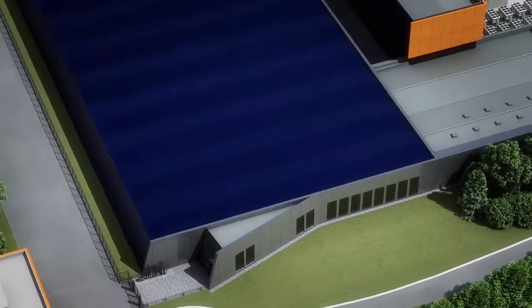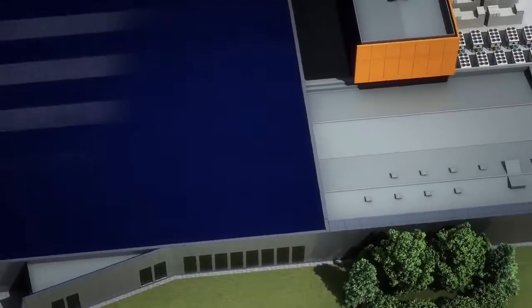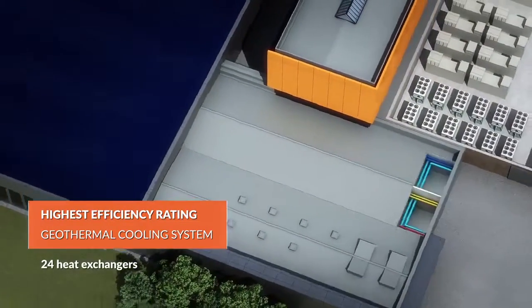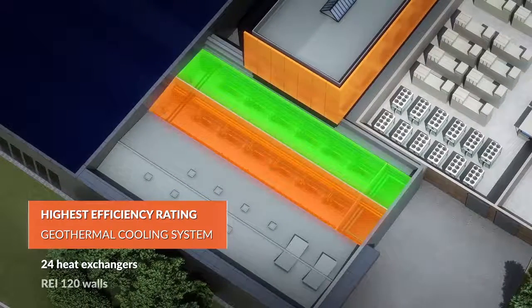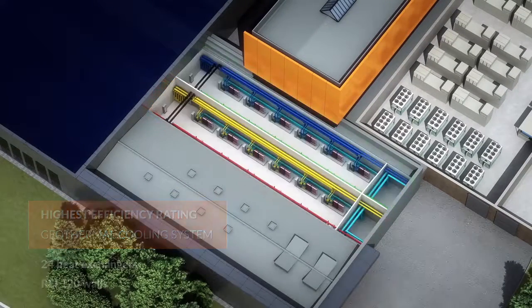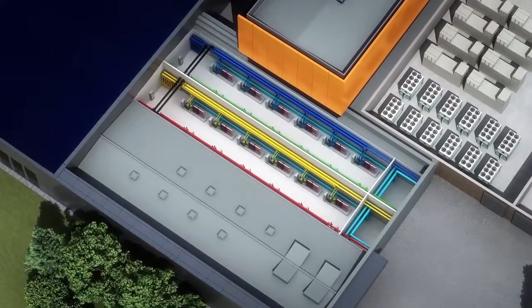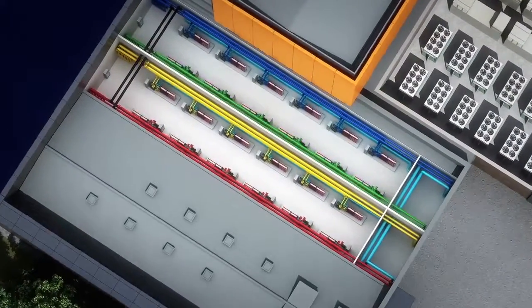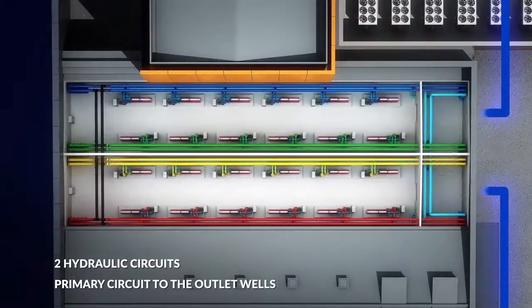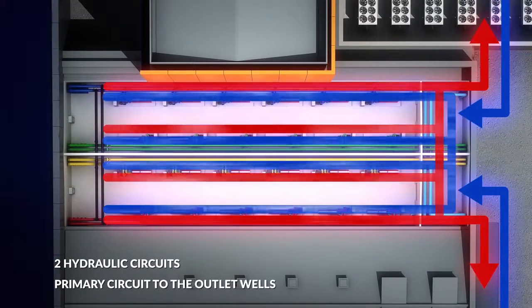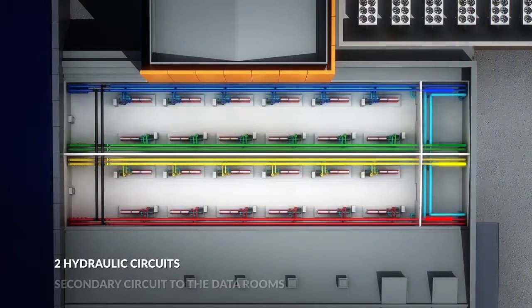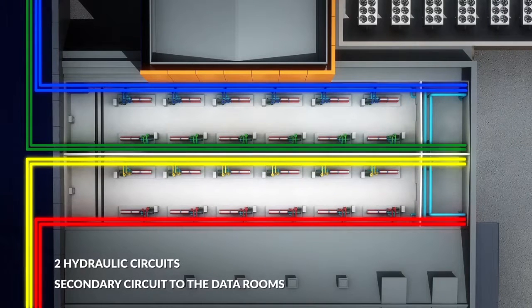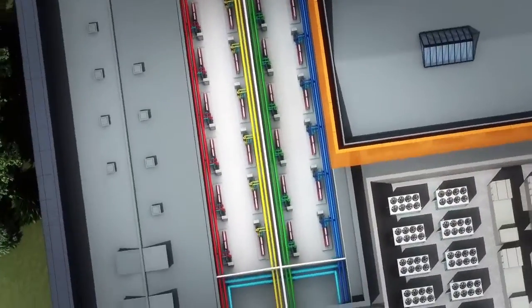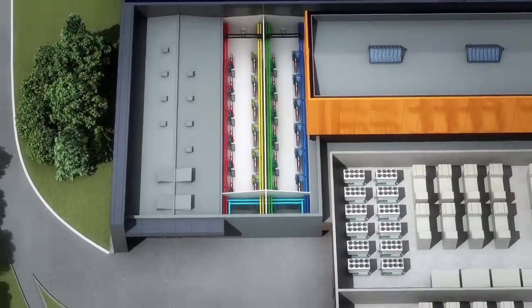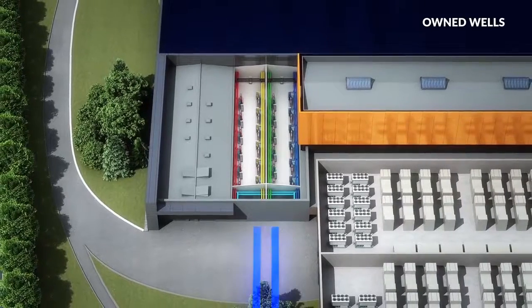The cooling system has a highly efficient geothermal function. The heat exchangers are located in 2 rooms dedicated to mechanical air conditioning, separated by firewalls. This is where the 2 hydraulic circuits are located. The primary circuit extends to the wells and the secondary circuit to the rooms. The cold water taken from the owned wells reaches the exchangers via 2 separate pipes.